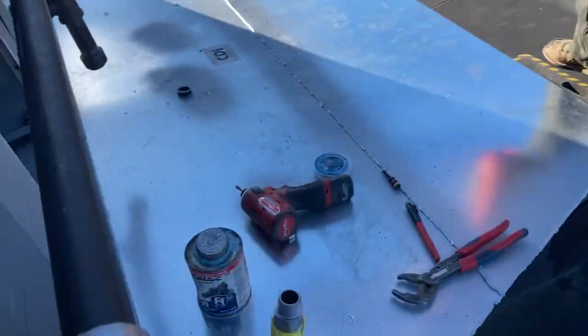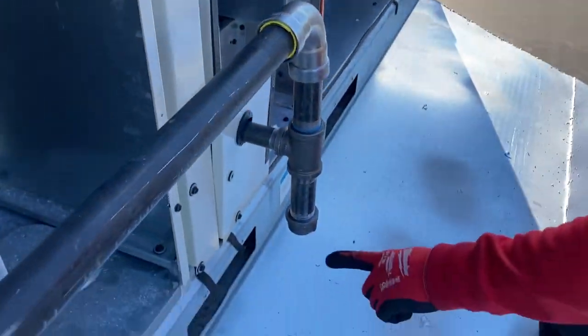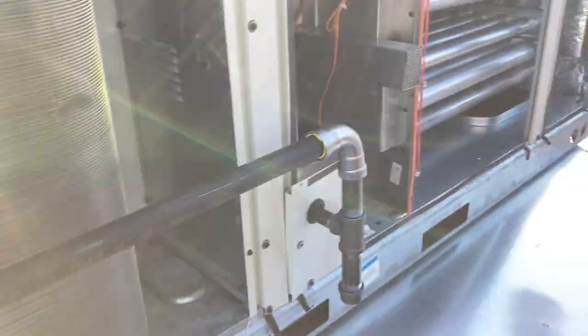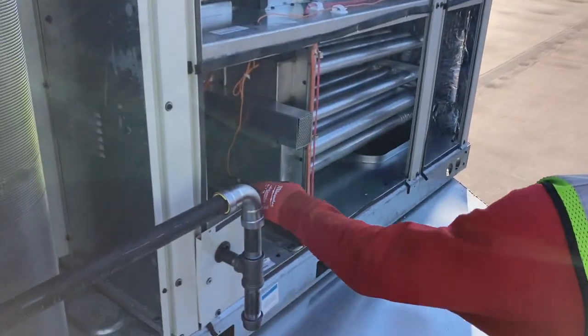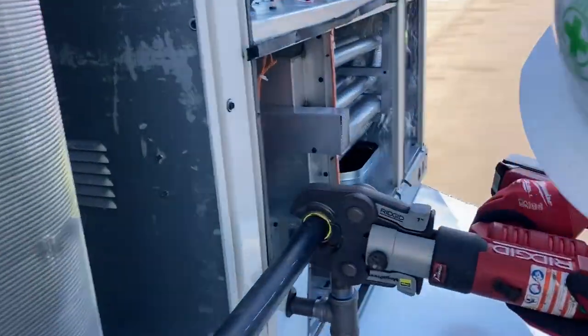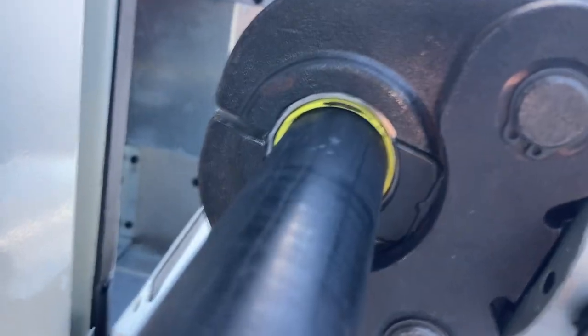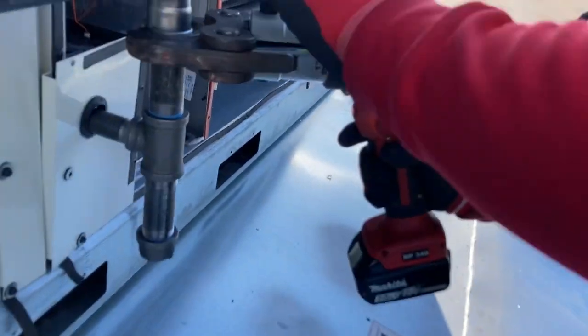In order to have a proper drip leg, in this case we had to come up, over, and then drop down — can't go straight in. So we had to do a drop with the drip tee and then go into the unit. It's a 1-by-3/4 black iron tee. We've got two more joints to do, then we're going to look at them all to make sure we did every single one. The union's inside the cabinet.